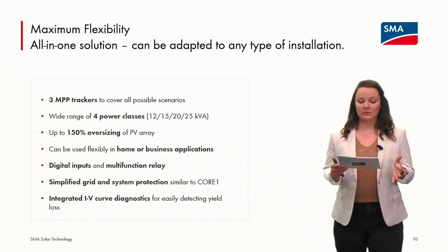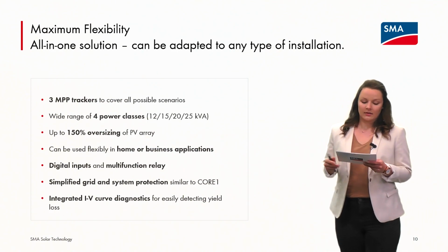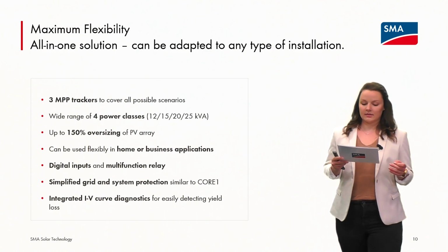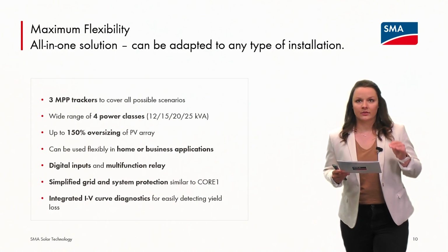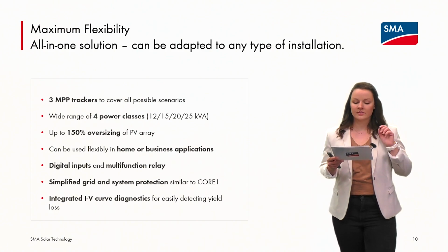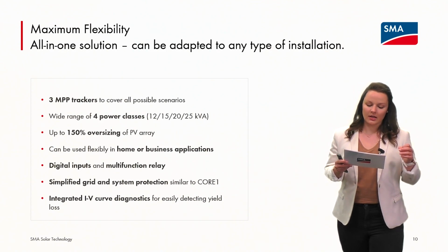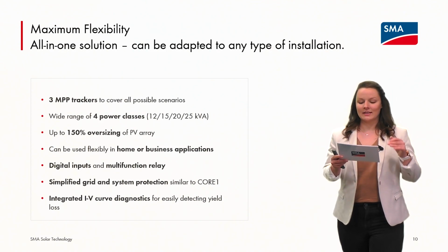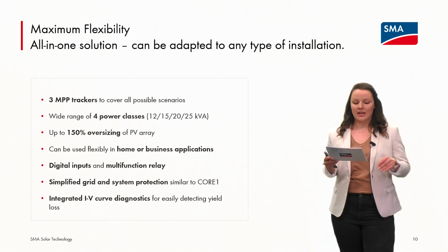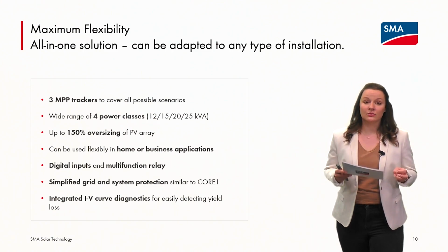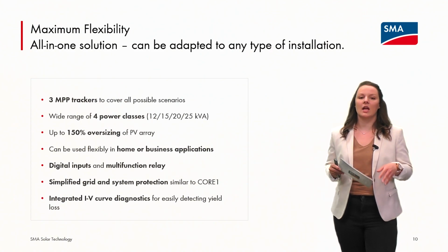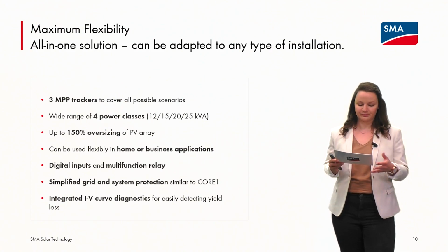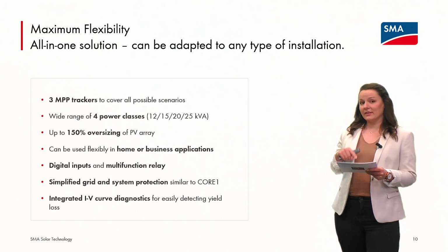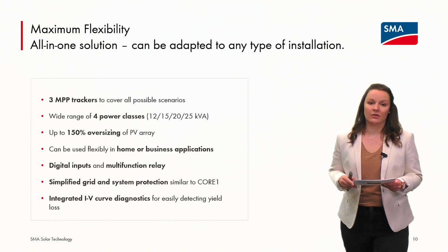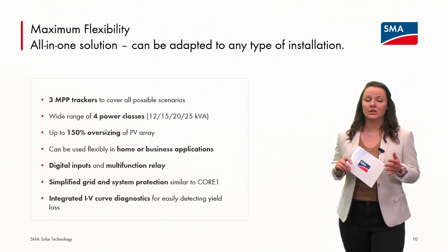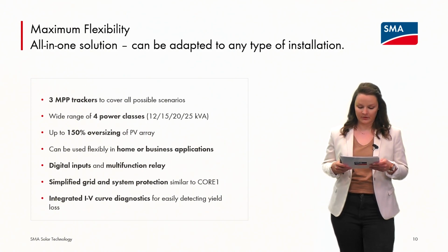What does maximum flexibility mean? The inverter offers 4 power classes, 12 to 25 kVA. It offers 3 MPP trackers with 24 amps input current each, and each MPP tracker has 2 string inputs, so in total we have 6 DC inputs. By having this, an overdimensioning of the PV plant of up to 150% is possible.